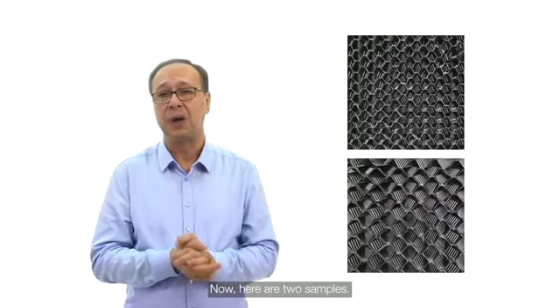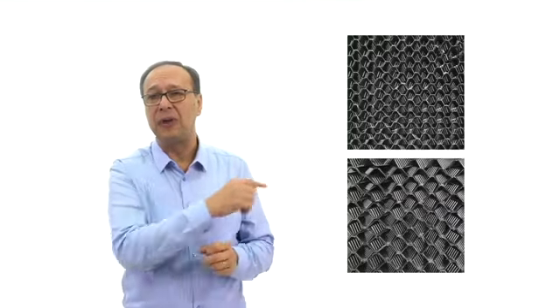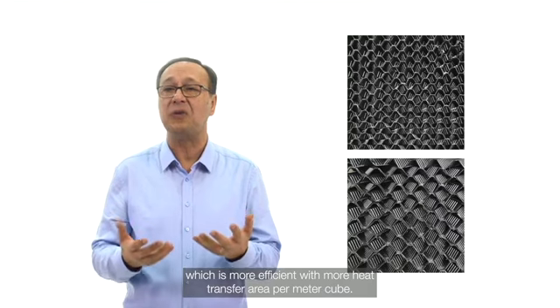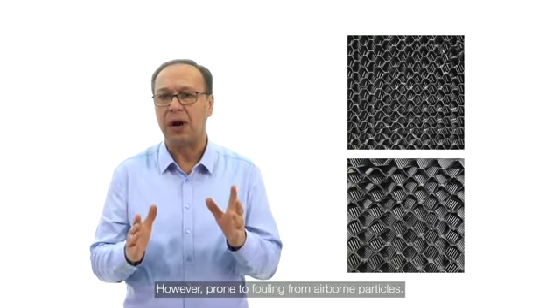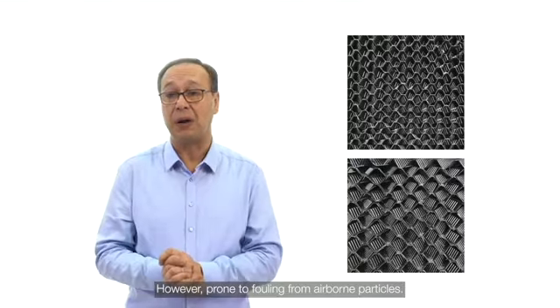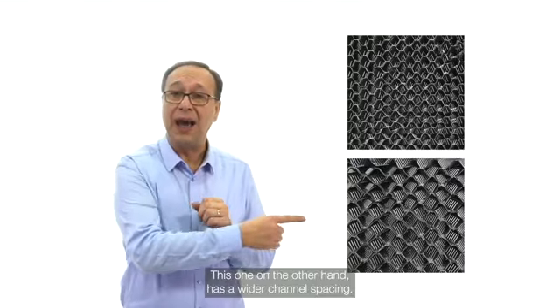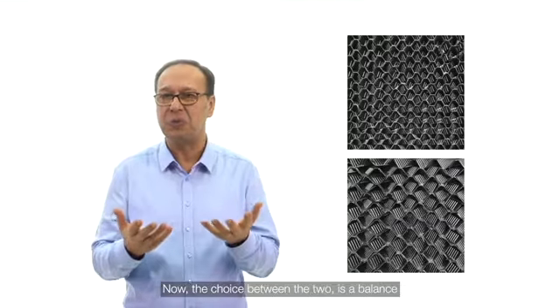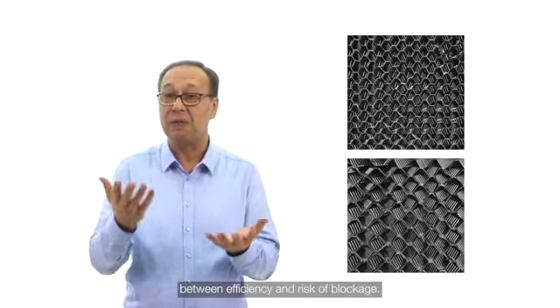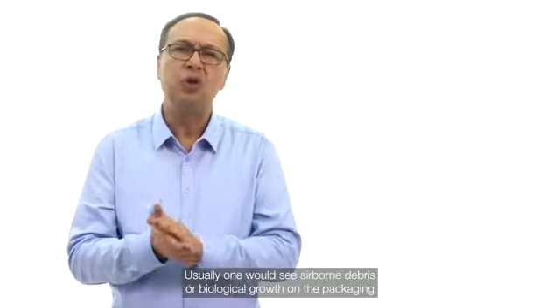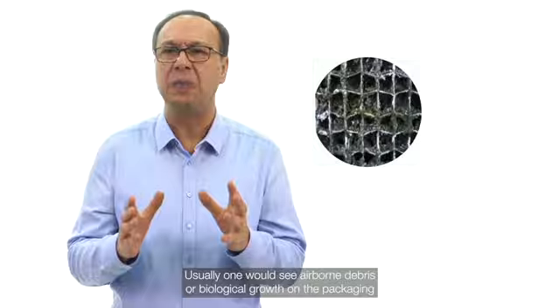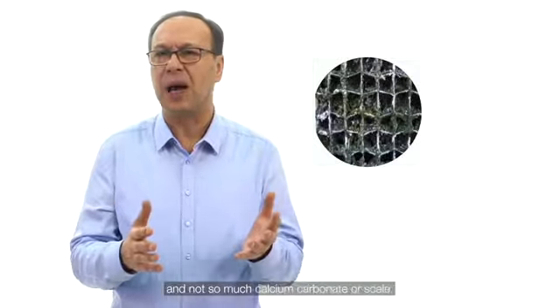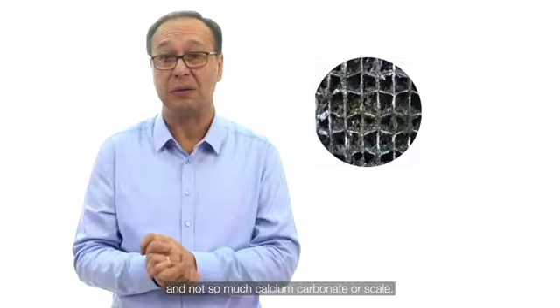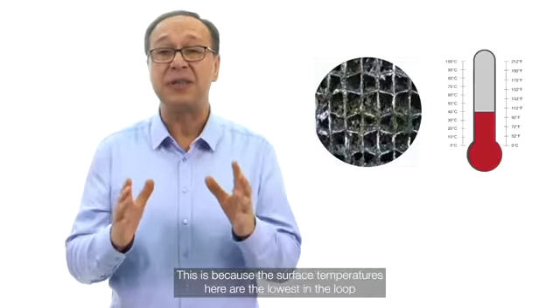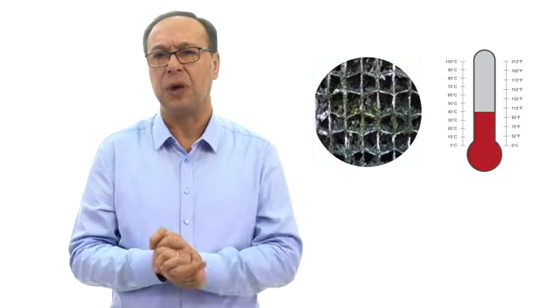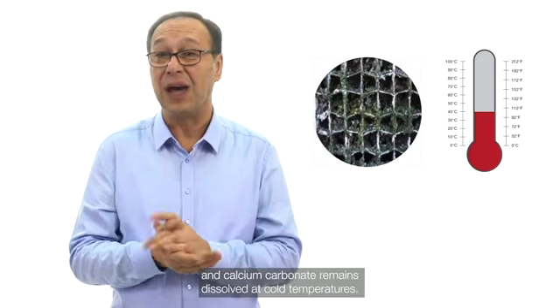Now, here are two samples. This one has a narrow channel spacing, which is more efficient with more heat transfer area per meter cube. However, prone to fouling from airborne particles. This one, on the other hand, has a wider channel spacing. Now, the choice between the two is a balance between efficiency and risk of blockage. Usually, one would see airborne debris or biological growth on the packing, and not so much calcium carbonate or scale. This is because the surface temperatures here are the lowest in the loop, and calcium carbonate remains dissolved at cold temperatures.